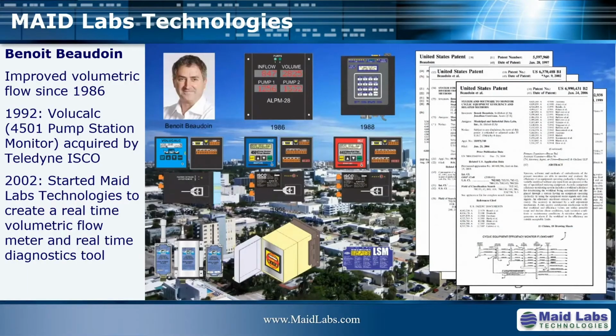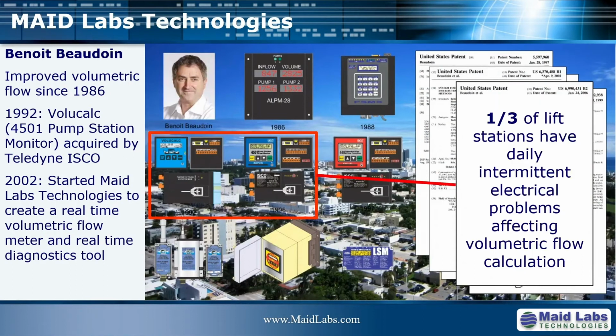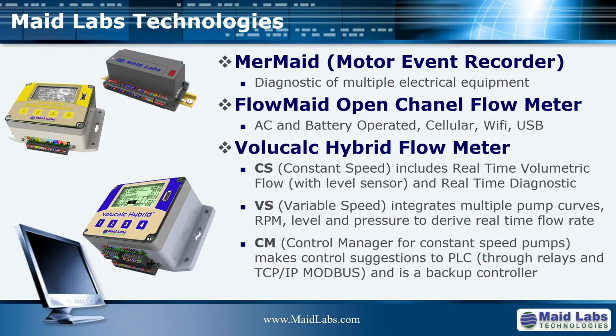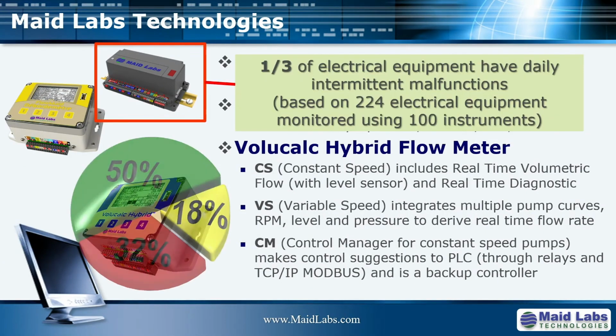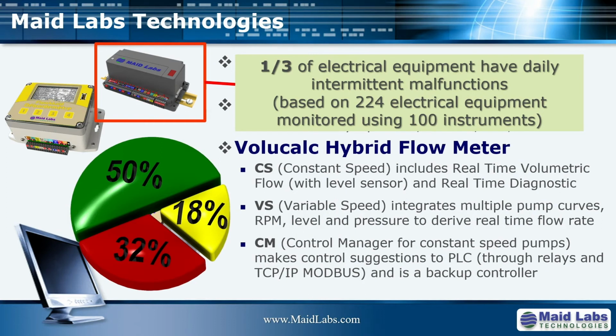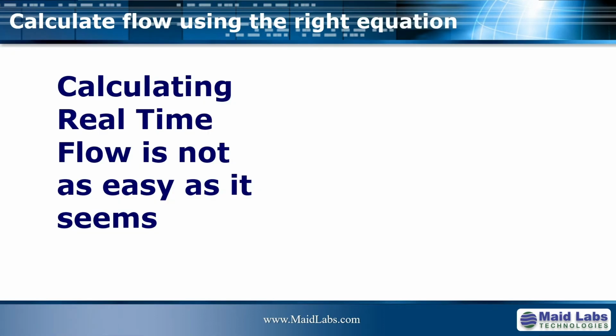I made a lot of volumetric flow meters during my lifetime. One of them made me discover that 1/3 of lift stations had daily intermittent electrical problems that were affecting volumetric flow calculations. Later on in my life, I continued to develop other products, and one of them made me discover that 1/3 of electrical equipment had intermittent electrical problems. So one thing I've learned with this is that electrical problems degenerate to the point where they can be discovered. When we calculate flow, you need to compensate for abnormal behavior.